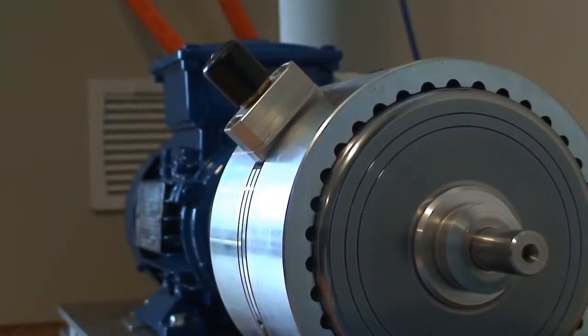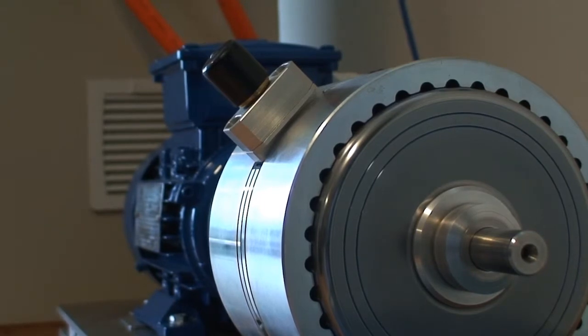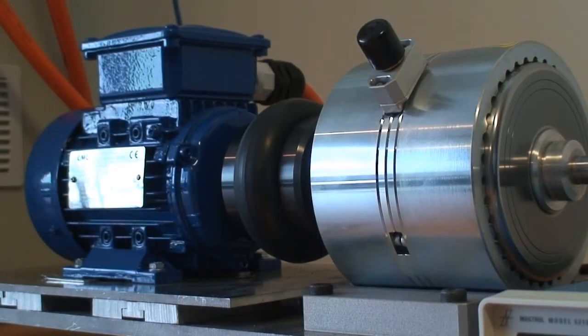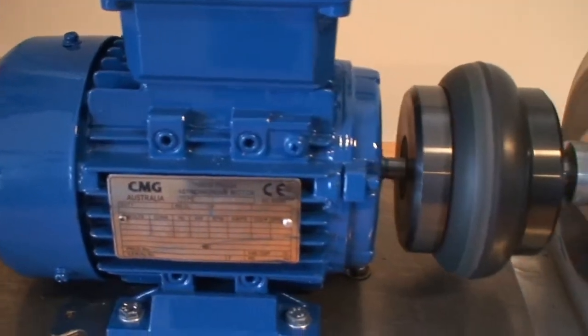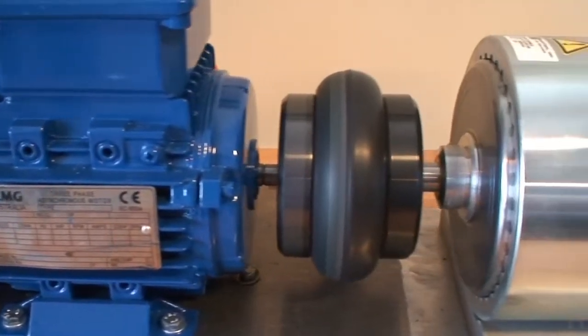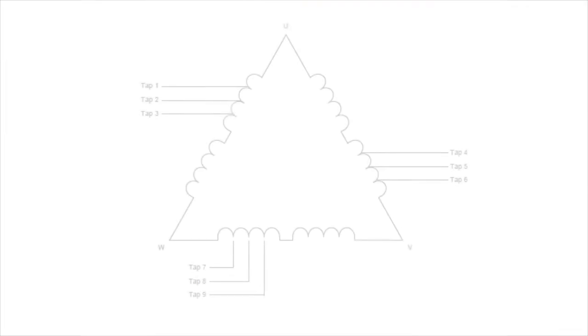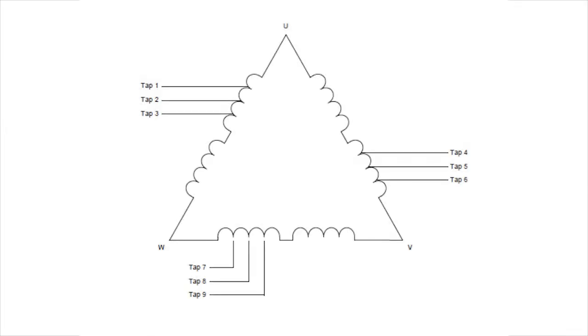This is the test motor. As we can see, the test motor is a small, three-phase, 180-watt induction motor. This motor has been rewound with a number of extra taps in the stator winding, so that the stator earth and turn-to-turn faults can be simulated.